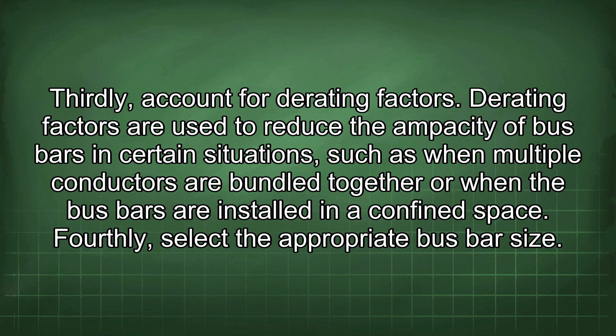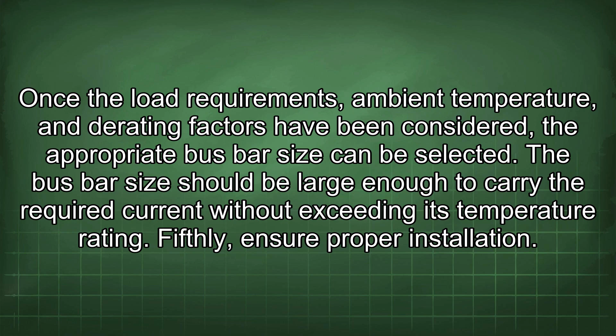Fourthly, select the appropriate busbar size. Once the load requirements, ambient temperature, and derating factors have been considered, the appropriate busbar size can be selected. The busbar size should be large enough to carry the required current without exceeding its temperature rating.